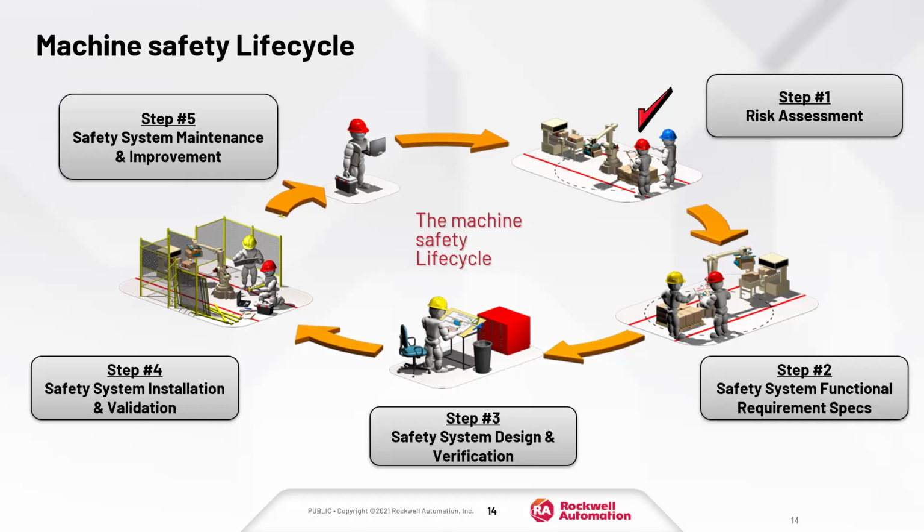It's a step process. So obviously, if you have a machine and someone has to interact with it, we call that a task. And so we do a risk assessment. The risk assessment is basically you have to first identify all the tasks that someone does with that machine. That could be an operator, it can be maintenance and repair, it could be simple people that are around it. I always notice when I go to plants, they have yellow lines, and they tell me to stay between them because I'm not part of the workforce. But sometimes people go outside of those yellow lines. So there again, you have to think about that risk. If someone steps out of the box and they walk into this machine, they don't know anything about it. Could they get hurt? So that task hazard pair relationship is probably the hardest thing to do.